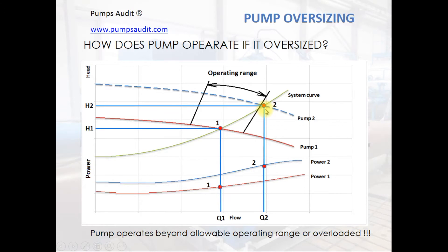This means that pump 2 will operate with lower efficiency and lower reliability. If we look at the power curve, we will discover that the electric motor can be overloaded. What can cause motor failure, despite the fact that it is more powerful than the motor of pump number one?